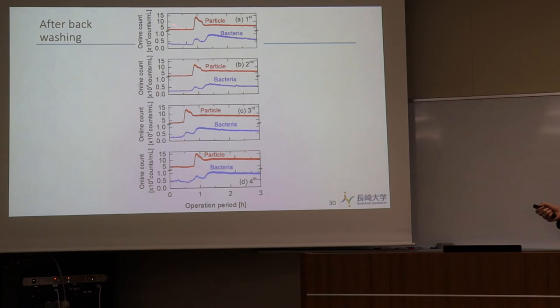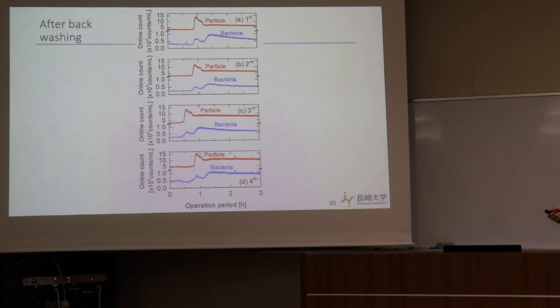Looking in detail at the period after backwashing: for particles there is one peak, but for bacteria there are two peaks — two increases. This pattern of two peaks follows all backwashing events, which is a good indicator that the bacteria counter is more sensitive to variation than the particle counter alone.